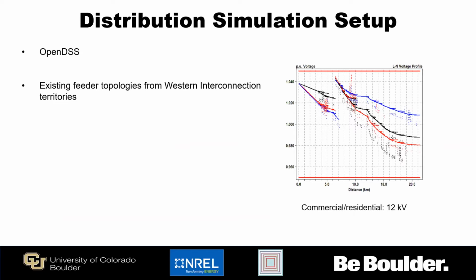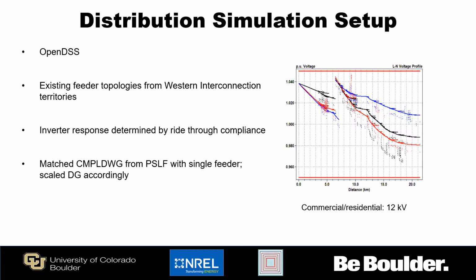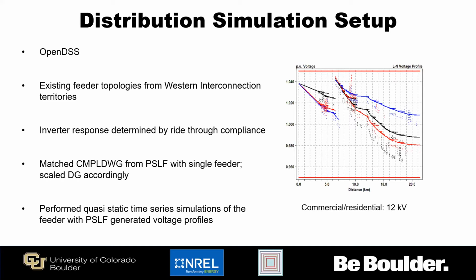This just shows on the right the voltage profile for a commercial/residential 12 kilovolt feeder, and you can see where the voltages at the end of the feeder are starting to get to places that are pretty close to tripping events. We are looking at the inverter response as it determines the ride-through compliance. We matched the composite load model in PSLF with a single feeder and then scaled the distributed generation on that feeder in a corresponding manner.